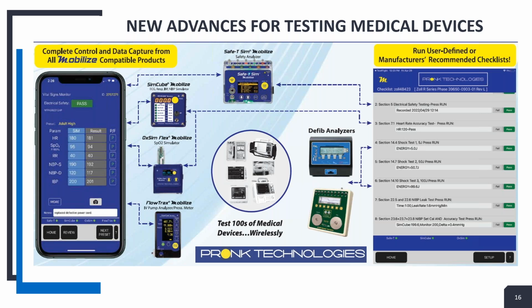The manufacturer requires us to do a wide range of discharge tests. What's the next test it wants us to do? So we'll do 50 joules and then hit run. You hit run, that will tell the analyzer to go and measure. Were you able to hit run? There should be a run button on the right.